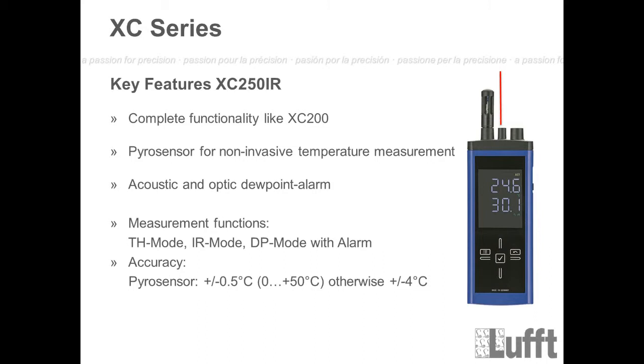So that means you have additional measurement modes or functions for the XC250, which is the TH mode, which is the standard XC200 measurement mode for temperature and humidity. Then you have the IR mode, which is the pyro sensor mode, and you have the dew point alarm mode in addition, right? The accuracy of the pyro sensor is plus minus 0.5 degrees Celsius between 0 and 50 degrees Celsius. Otherwise, the accuracy is plus minus 4 degrees Celsius.